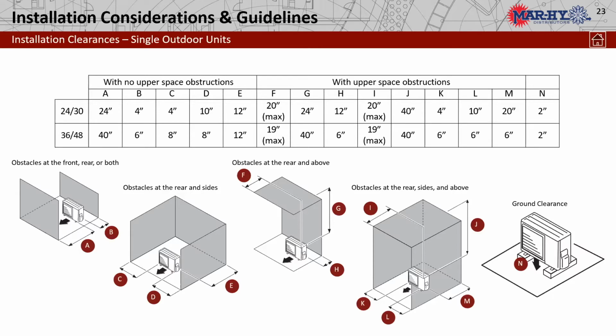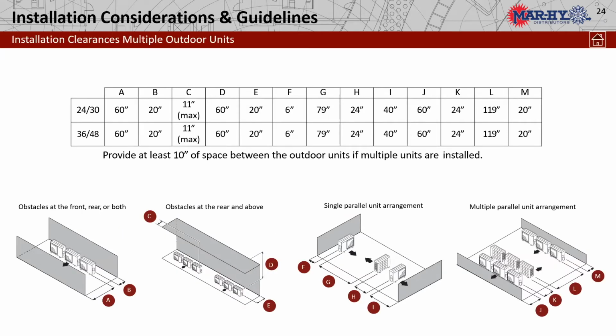Do keep those clearances in mind. That'll probably be the ones most applicable for our installs, just backing up to the house, giving it 4 inches for the 2 and 2.5 ton and 6 inches for the 3 and 4 ton. In multiple outdoor unit applications, the install instructions will show you how to lay those out, whether it's a rooftop installation or the side of the building, how much room you'd need between them, what obstacles are in your way, and how to space these out to make sure we get the airflow necessary for good heat exchange.